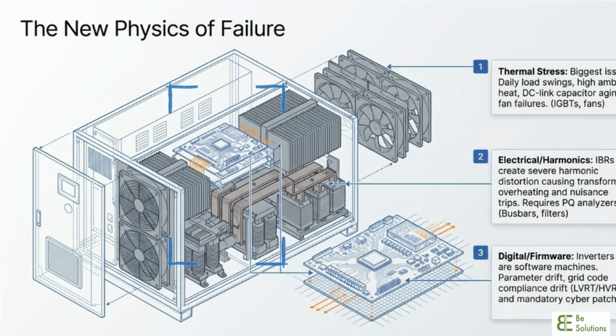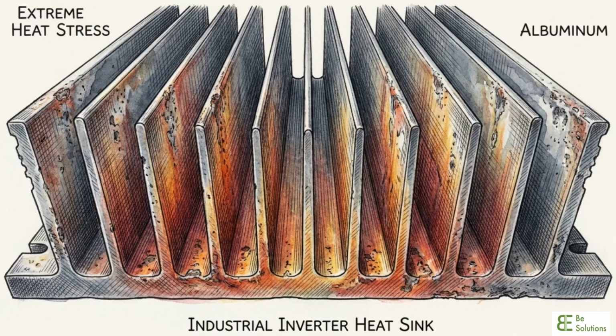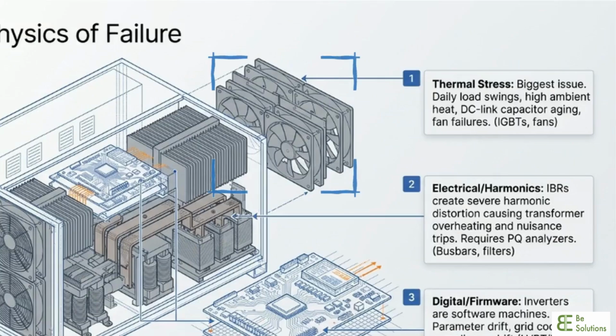This exploded view of an inverter cabinet illustrates what engineers call the new physics of failure. The first major threat is thermal stress. Components like high-power insulated gate bipolar transistors and DC link capacitors are repeatedly subjected to massive daily load swings and high ambient temperatures, leading to accelerated physical degradation.